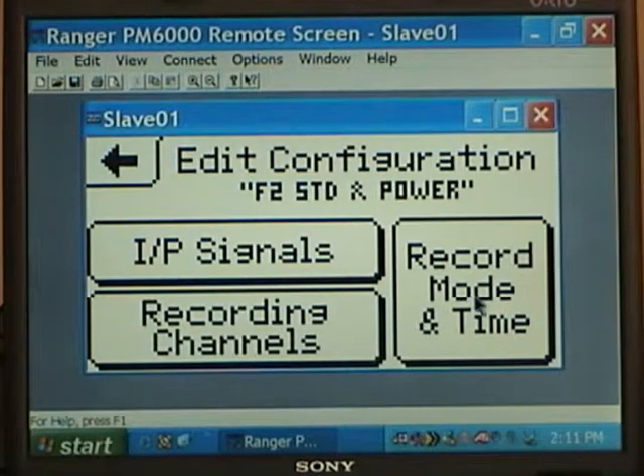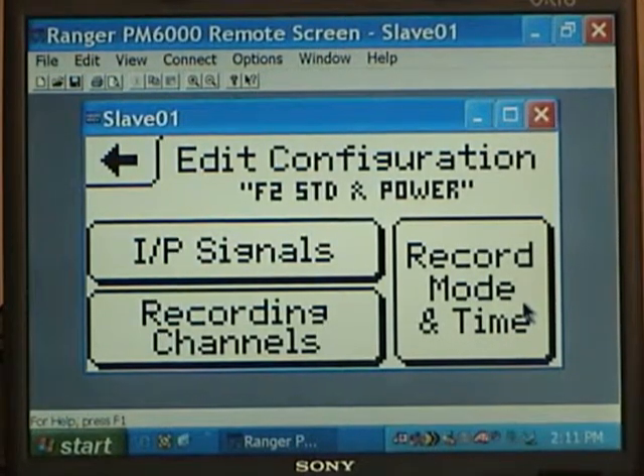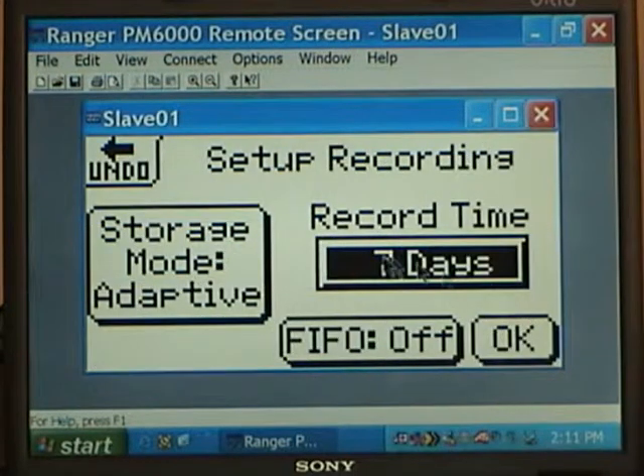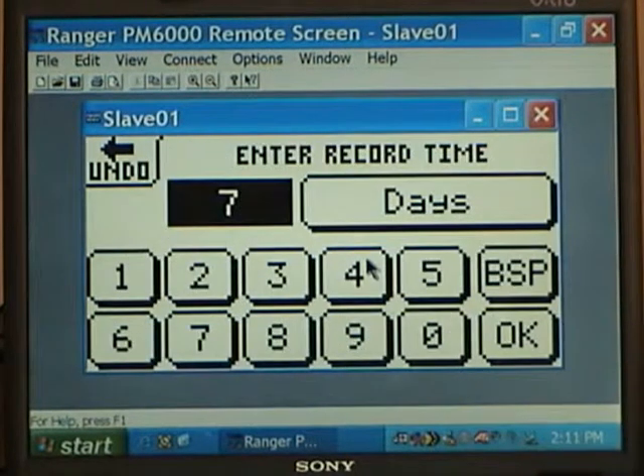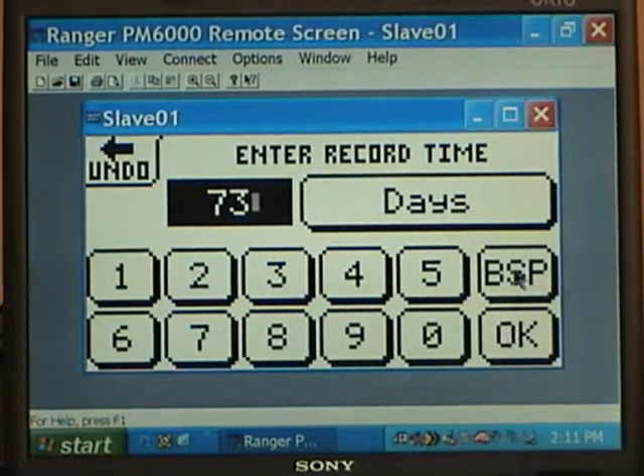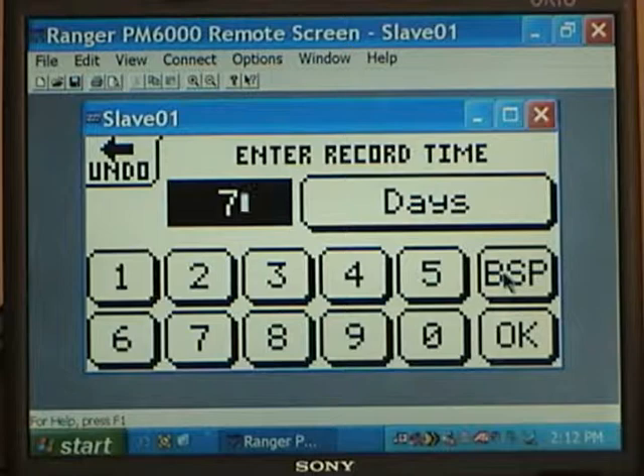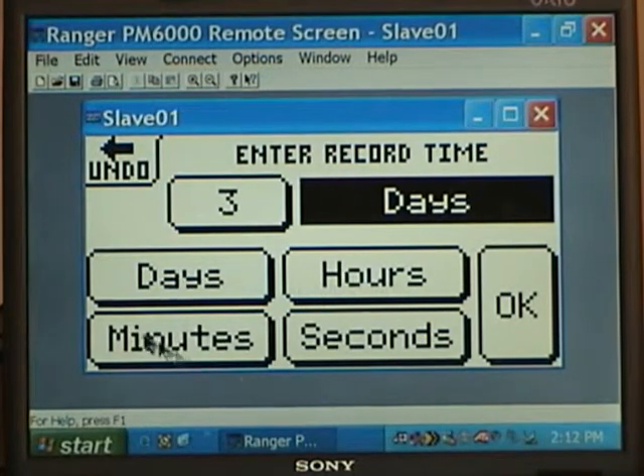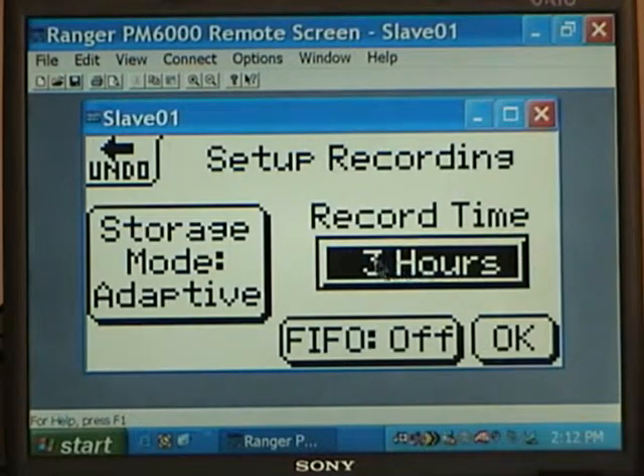you can change the record mode and time. This is where we explained that you can record, and the standard time is set up for 7 days, but you can change the 7 days to whatever you want just by clicking on it and plugging in whatever is appropriate. Like I could backspace and clear it. I could put in 3, and if I click on days here, it gives me choices of days, hours, minutes, or seconds. So if I wanted it to be 3 days, I could click on days. If I wanted it to be 3 hours, I could change it to 3 hours and then say OK. And now we've changed from 7 days to 3 hours.